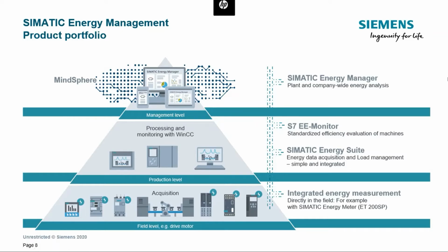For the acquisition, we have most of the devices that we can use, say Siemens devices, and those devices can be power meters. We can acquire energy information directly from, for example, VFDs, or directly on the controller level. We have I/O modules that are energy meters that can acquire energy measurements directly through the controller. There are different ways, and even non-Siemens devices can definitely be integrated and provide information in terms of measurements.